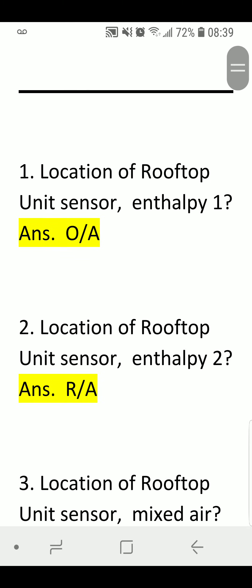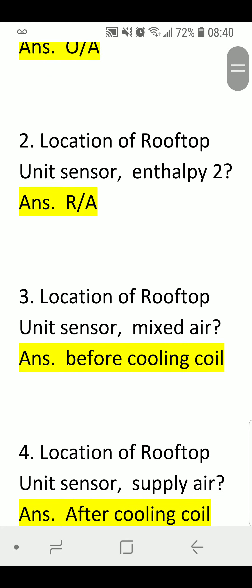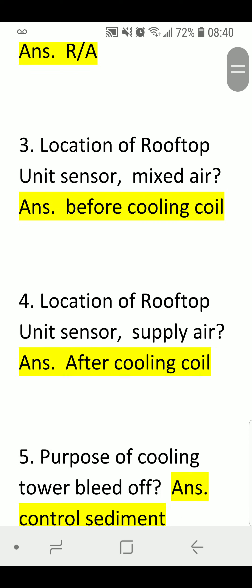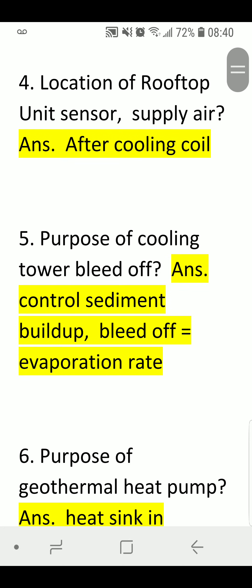Location of Rooftop Unit Sensor — Enthalpy 1: Answer: Outdoor Air. Enthalpy 2: Answer: Return Air. Mix Air sensor: Answer: Before Cooling Coil. Supply Air sensor: Answer: After Cooling Coil.